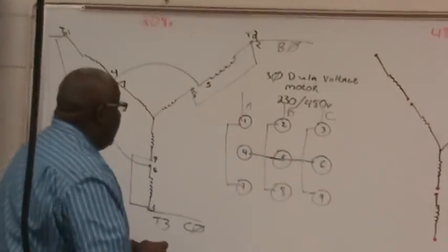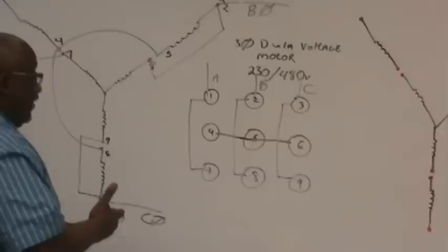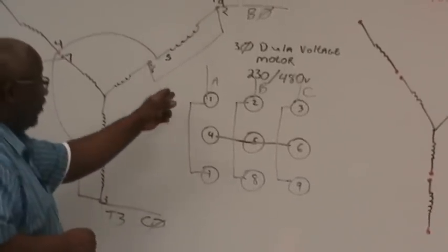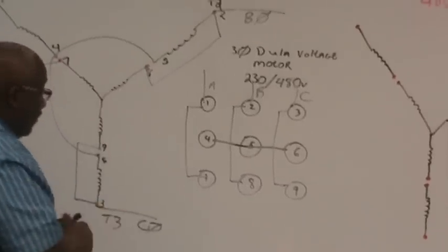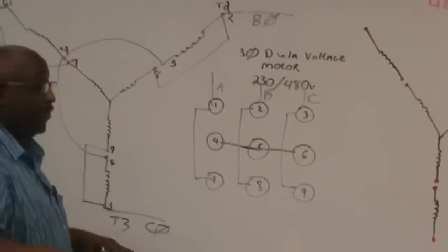Now, this will actually give you a clockwise rotation if you're sure that your phases are in that order. If you need the motor to reverse its rotation, it is easy to just go in and swap any two terminals.